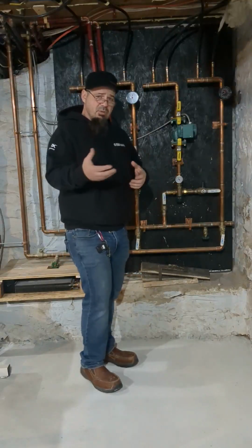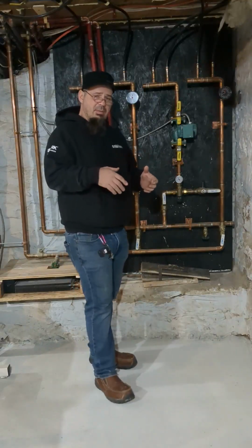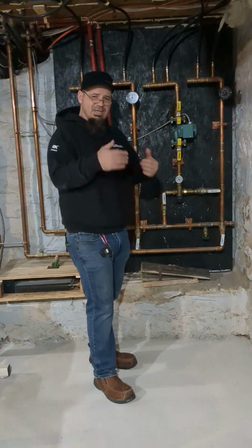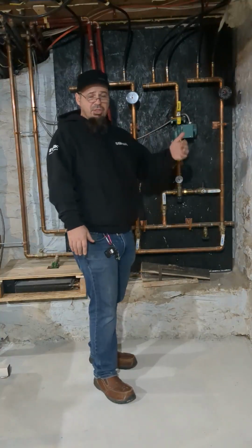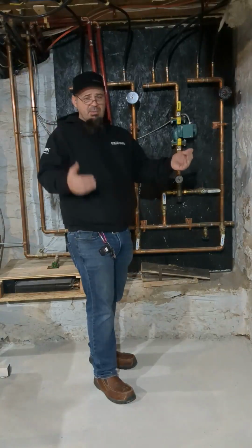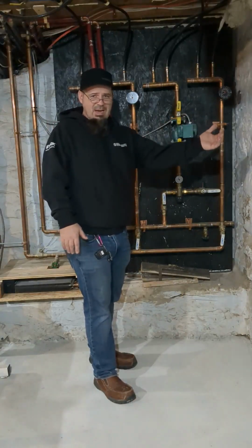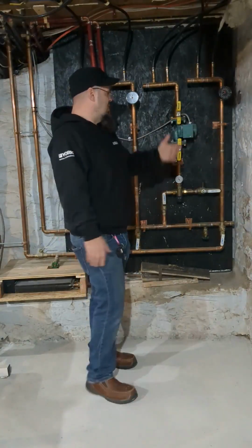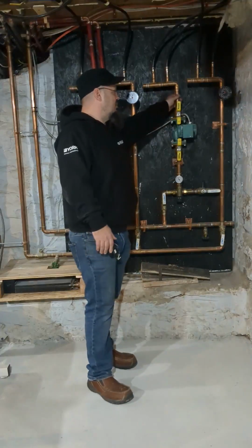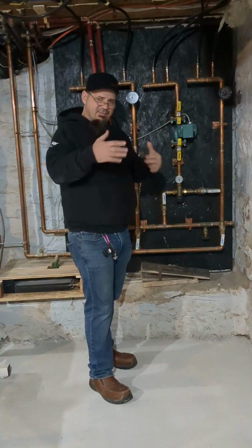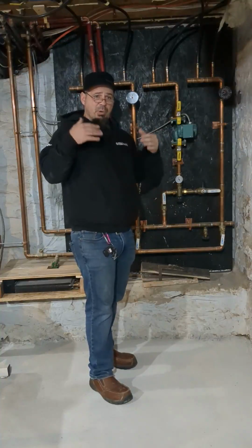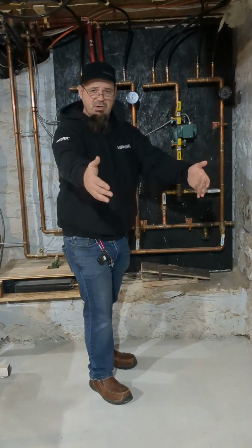Because what we do in all heating and cooling applications is set what's called a delta T. Delta T is the differential between your outgoing something and your incoming something. So in air, your supply air temperature versus your return temperature. In water, it's going to be your supply water versus your return water. And the delta T is the difference that is created by you putting that energy into the space that you're conditioning.